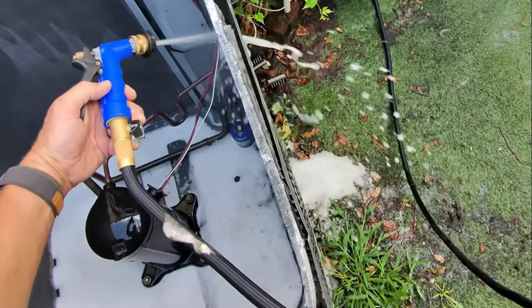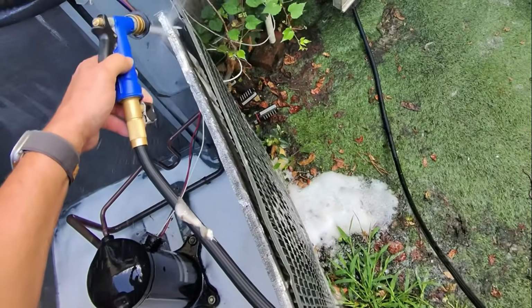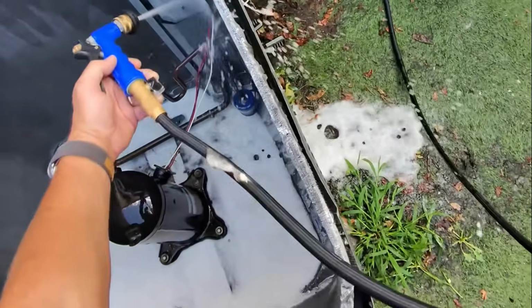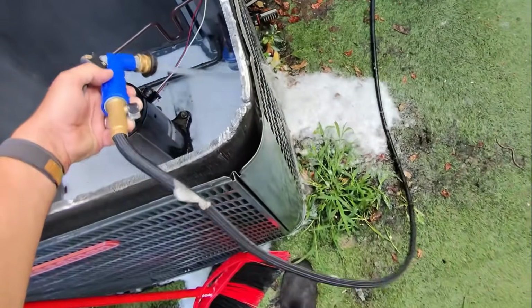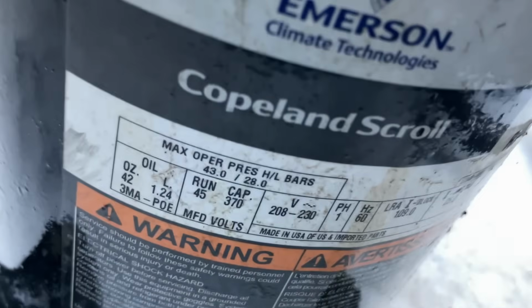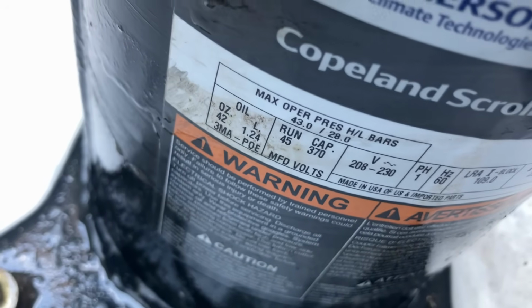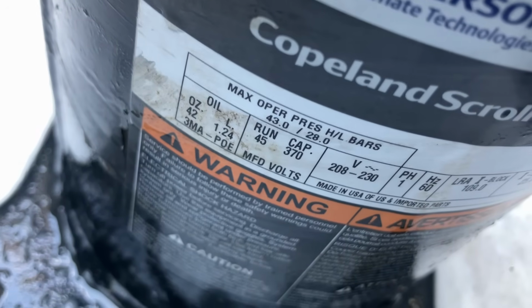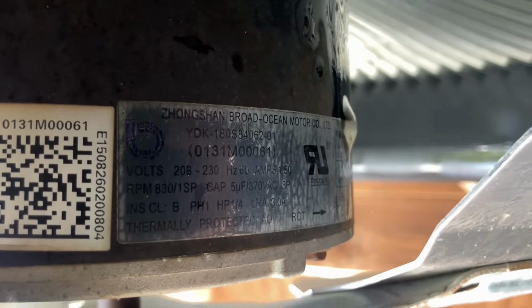Damn. It's unbelievable how this was literally just cleaned. Literally just cleaned about 2.5 months ago. Crazy. All right, I've thoroughly rinsed all the chemical off the coil. Before I put the cover back on, I'm going to make note of my capacitor size for the compressor. See if I can see that in there. Let's see, 45, 370. All right, and then also let's check out our condenser fan motor if we can. I can hardly read it, but I'll take a picture of that and reference it.